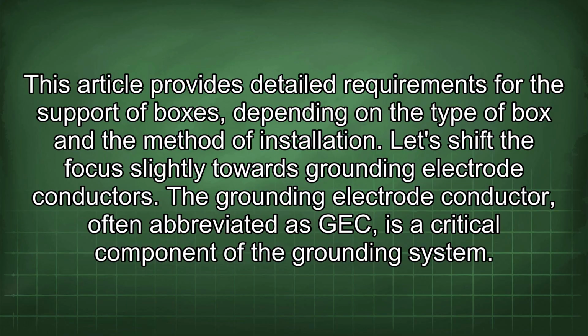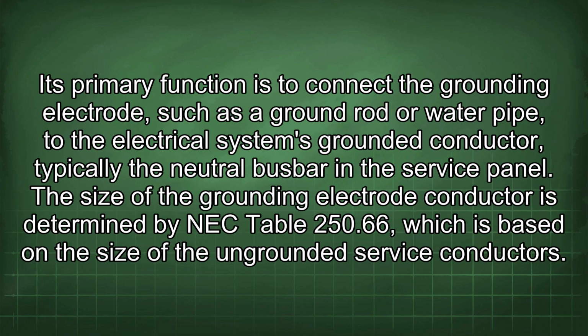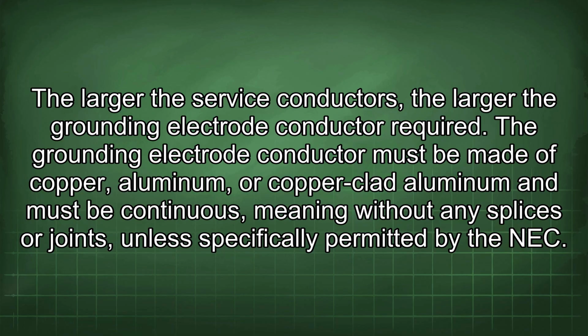Let's shift the focus slightly towards grounding electrode conductors. The grounding electrode conductor, often abbreviated as GEC, is a critical component of the grounding system. Its primary function is to connect the grounding electrode, such as a ground rod or water pipe, to the electrical system's grounded conductor, typically the neutral busbar in the service panel. The size of the grounding electrode conductor is determined by NEC Table 250.66, which is based on the size of the ungrounded service conductors. The larger the service conductor is, the larger the grounding electrode conductor required.